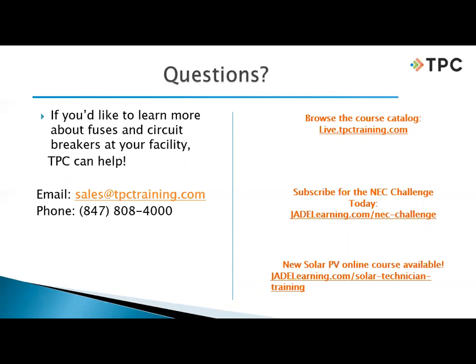Well, that's a great question, and I'm going to go on my experience. We put in some SWD circuit breakers in schools back in the 70s, and the gym teacher would come in dressed in shorts and a t-shirt and be turning the gym lights on with SWD breakers. Those were installed back in the 70s. Here it is, 2021, and those same breakers are still turning on the same lights. No issues. So it goes back to this: if they've been maintained properly, there should be no issue.